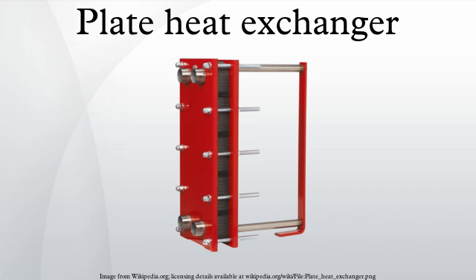Flow distribution and heat transfer equation. Design calculations of a plate heat exchanger include flow distribution, pressure drop and heat transfer. The former is an issue of flow distribution in manifolds. A layout configuration of a plate heat exchanger can usually be simplified into a manifold system with two manifold headers for dividing and combining fluids, which can be categorized into U-type and Z-type arrangement according to flow direction in the headers, as shown in the manifold arrangement. Bassiouny and Martin developed previous theory of design. In recent years, Wang unified all the main existing models and developed a most complete theory and design tool.